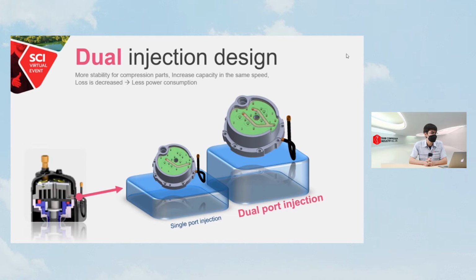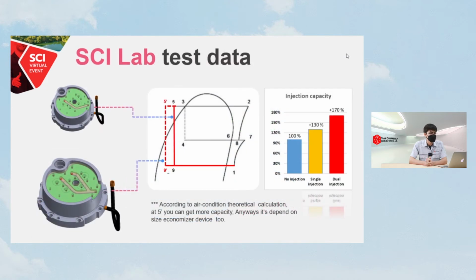With the dual injection, our compressor for the APF standard is equipped with a dual injection design, which provides more stability or increased capacity at the same speed, less discharge temperature, and less power consumption. When we talk about the injection, you will see the red line in the pH diagram. The dual injection extends the cooling line and provides you more capacity even when the compressor is running at the same speed, which leads to a better COP. The right-hand side graph is the injection capacity comparison, and we get up to 70% more injection capacity compared to a compressor with no injection.